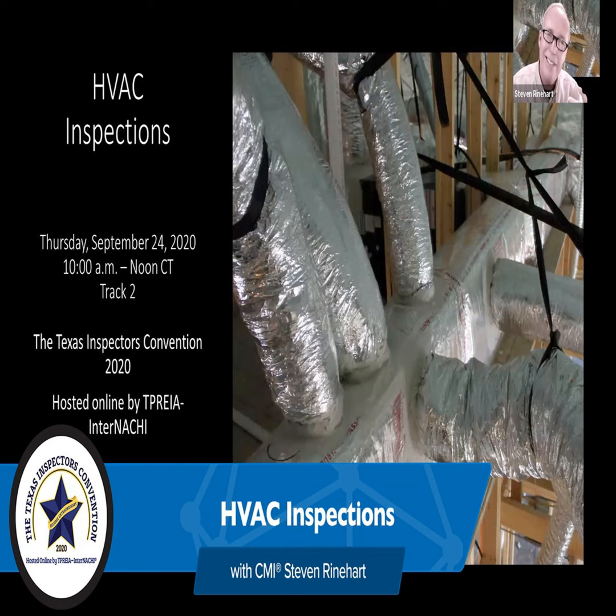And you've got a controller. Mechanical code says if you're using the air handler for fresh air, it has to be controlled. And it needs to be able to be disabled by the occupants when they don't want fresh air. That's a very common Honeywell, but it's pretty easy. It programs in, you put in the size of the vent, how much air it's moving, how many people live in the house, square footage, and it computes the ASHRAE 62 standard for fresh air.